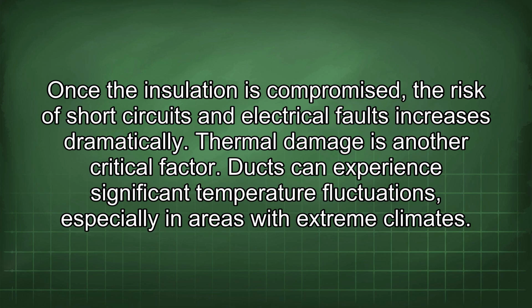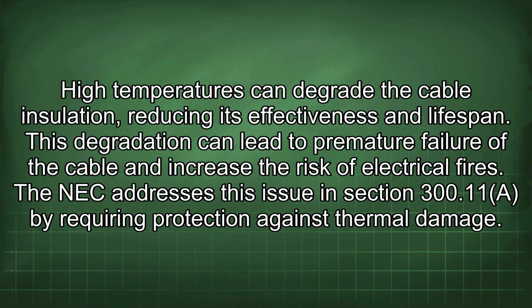Thermal damage is another critical factor. Ducts can experience significant temperature fluctuations, especially in areas with extreme climates. High temperatures can degrade the cable insulation, reducing its effectiveness and lifespan. This degradation can lead to premature failure of the cable and increase the risk of electrical fires. The NEC addresses this issue in Section 300.11 by requiring protection against thermal damage.